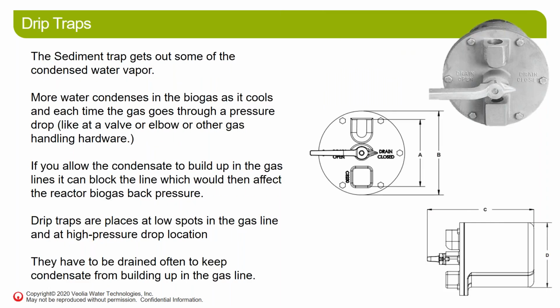Drip traps: the sediment trap gets out most of the water, but as you have your piping along the system going to the flare, going to your biogas utilization, the boiler, whatever, over the length of the lines you're going to accumulate condensate. So you have to have these drip traps at low points or along certain lengths of pipe. If you don't drain that water out along the piping, it'll build up, block the line, and possibly cause gas blockages and pressure increases. So these drip traps are placed all along the lines, and they have to be drained. Check these things, make sure they're working during operation, and have it as a routine maintenance task to go and drain them. But when you're down for maintenance, also check and make sure they're working properly, and you can replace them.